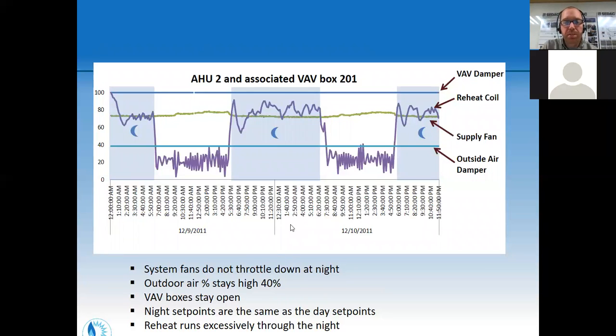Here's an example of an air handler that had the schedules reversed. At night, it's heating to a nice temperature, and during the day it's setting back in the wrong direction. So it just had day and night reversed. It wasn't terribly uncomfortable. This is the reheat coil - it's open at night and closed during the day.